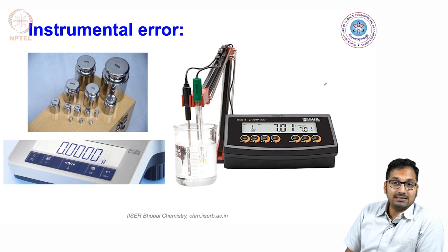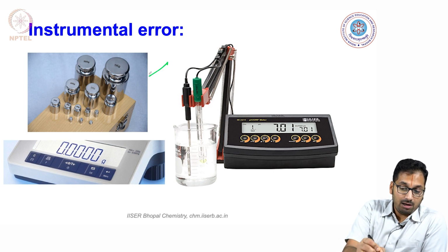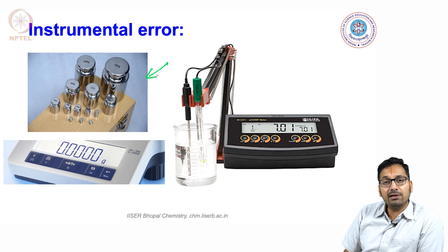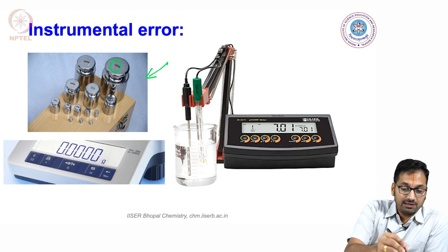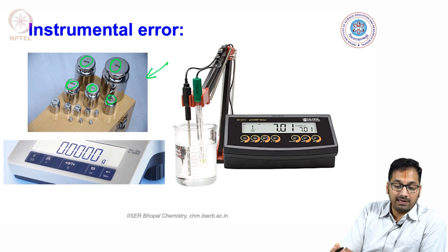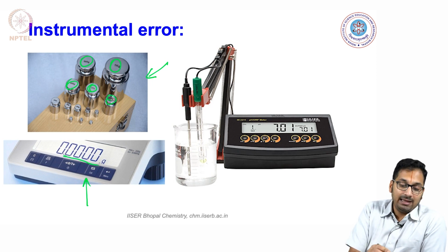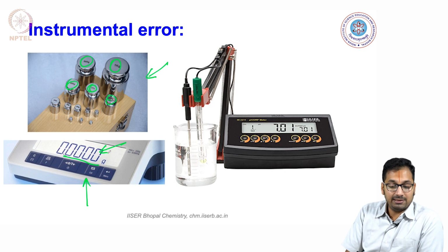Okay, the weighing balance, as I said, could also result in an error. So what generally gets done is that with these weighing balances, one would end up using standard weights that have a specific mass in grams associated with them, which when calibrated against the weighing balance you end up using would help you ensure a lesser amount of error would come up in the weighing balance. And most often, as you are able to see a digital weighing balance here, the number of digits that they end up displaying indicates the uncertainty comes up in the last digit.